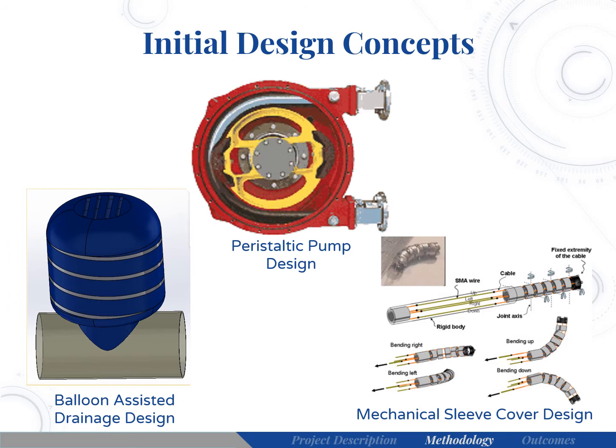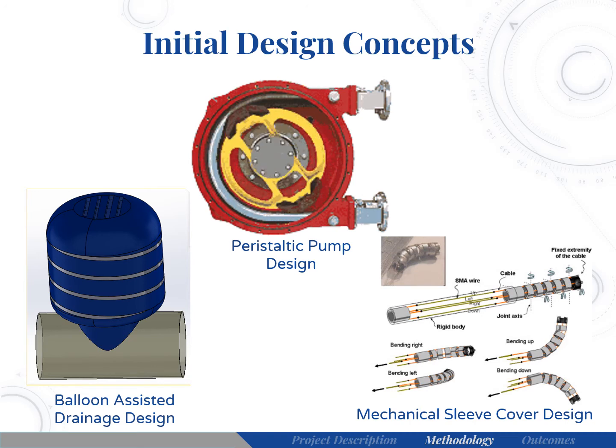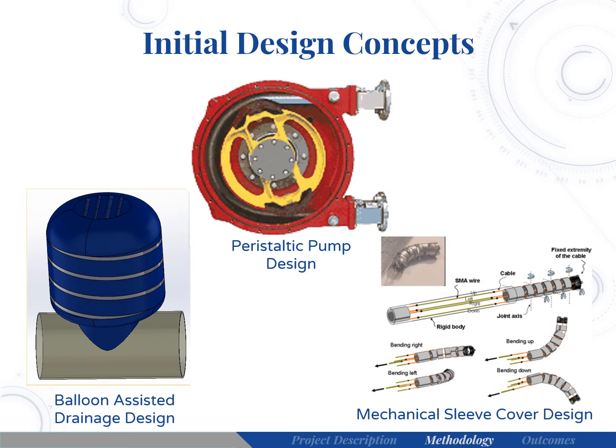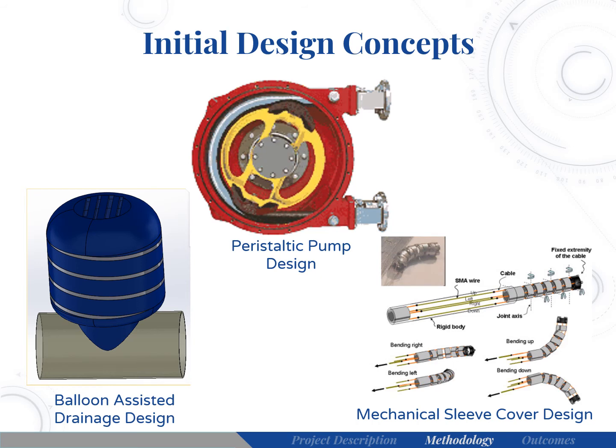While the valve is open, urine will naturally pass as previously has occurred. However, when the motor activates, the balloon is compressed, closing the valve to prevent retrograde flow towards the bladder. This impulse of air rapidly increases the pressure in the Foley catheter, which will expel the stagnant urine into the collection bag. When the motor deactivates, the balloon passively refills and the valve naturally opens.